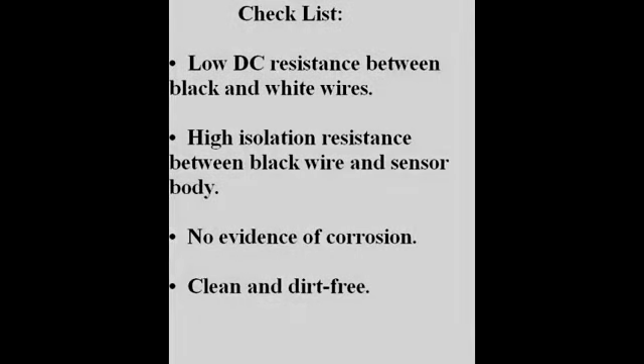If the DP-15 has low DC resistance between the black and white wires, has a high isolation resistance between the black wire and the metal case, has no evidence of corrosion on the lid welds and has been cleaned of any dirt or contaminants, it can be reassembled and calibrated.